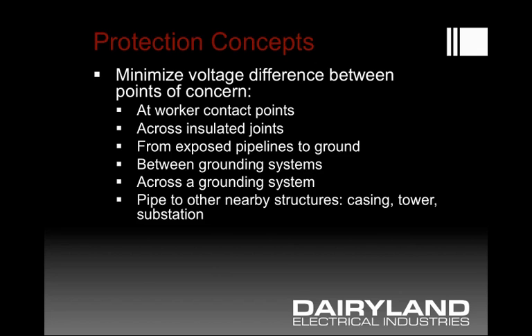There are a number of protection issues that come up in this topic. Basically, the concern is minimizing voltage between two points. It could be two points that a worker could get across, it could be the voltage difference across an insulated joint from one side to the other, between a pipeline and ground, or even between grounding systems or across a single grounding system where a voltage gradient could exist in the earth.